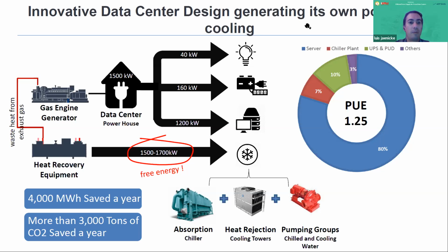Now, this 1.5 megawatt of power will be produced by the gas engine, which will be releasing a lot of energy in terms of exhaust gas and jacket water. All that heat is going to be recovered in the heat recovery equipment, and it will be sent to the absorption chillers that will transform this thermal energy into the cooling capacity required by the data center. Roughly for a 1.5 megawatt engine, there is enough heat in the engines to produce around 1.5 to 1.7 megawatts of cooling, which is roughly enough to feed the data center cooling needs.